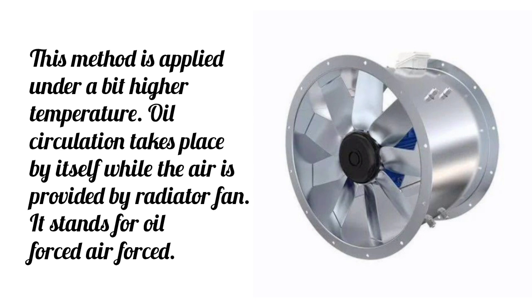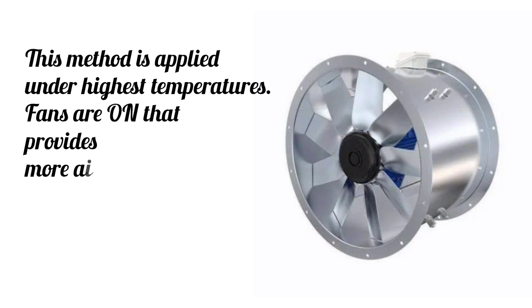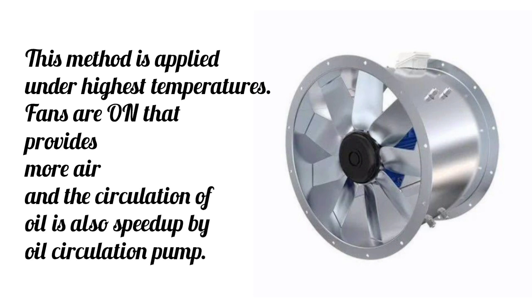OFAF stands for oil forced air forced. This method is applied under the highest temperatures. Fans are on, which provides more air, and the circulation of oil is also sped up by an oil circulation pump.